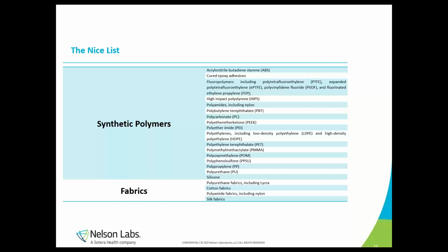The truth of it, though, is that the best way to address it from a scientific standpoint is not best from a timing and cost perspective. Because really, what you should do is perform extractables and leachables on a brand new device, real-time age that device, and then do extractables and leachables on the end product and compare them. You could do accelerated aging, but there's some discussion about the true leachability differences, so you could do all three. Honestly, though, we don't have anybody doing that just because of time.